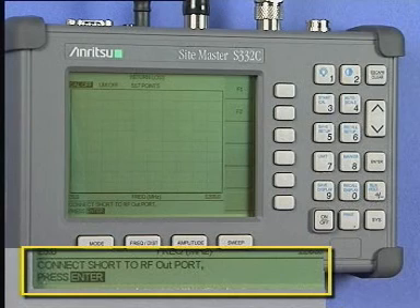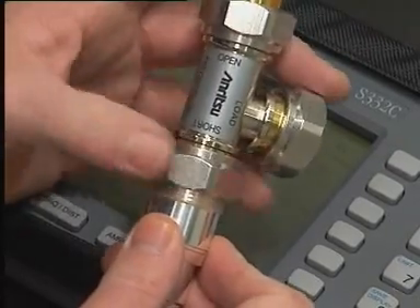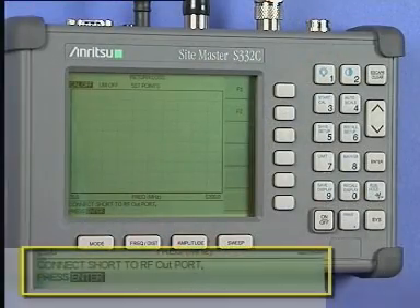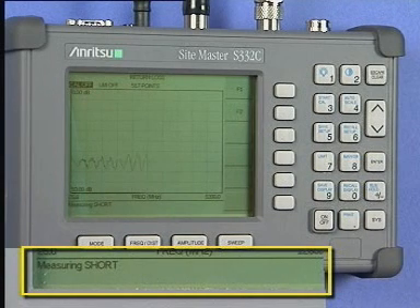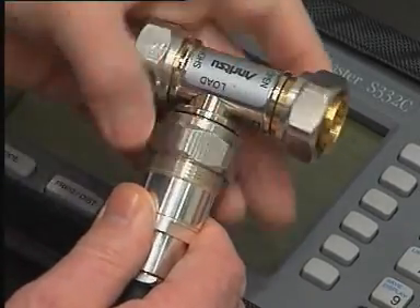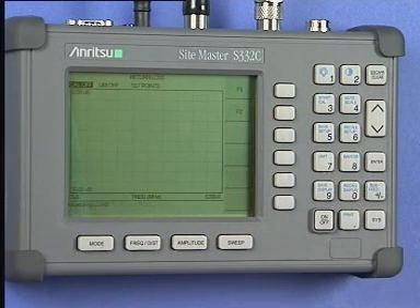After a few moments, the Site Master will prompt you with the message 'Connect Short to RF Out', which is asking you to connect the calibrated short circuit to the extension cable. When you have done this, press the Enter key and the instrument will again sweep and measure. After a few moments, the Site Master will prompt you with another message 'Connect Load to RF Out', which is asking you to connect the calibrated 50 Ohm dummy load. When you have done this, press the Enter key and the instrument will once again sweep and measure.